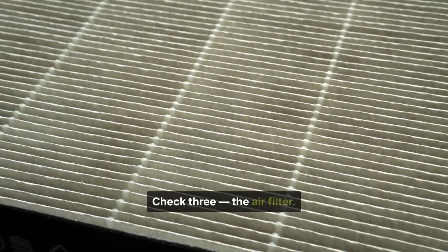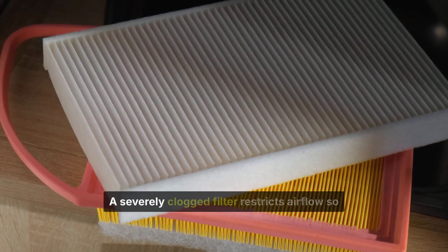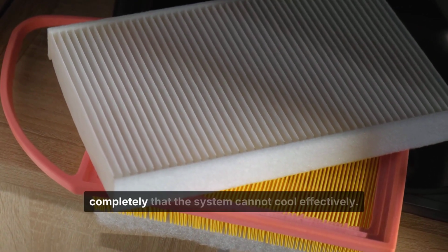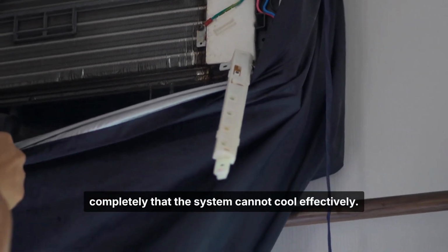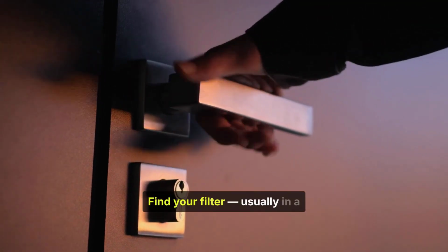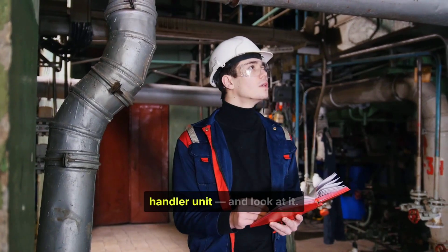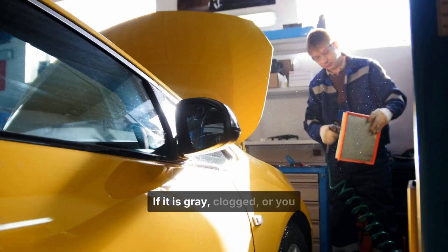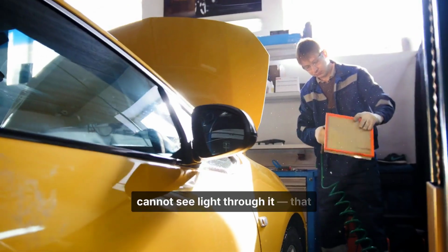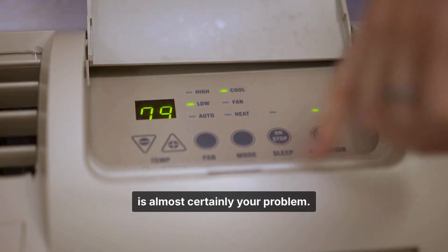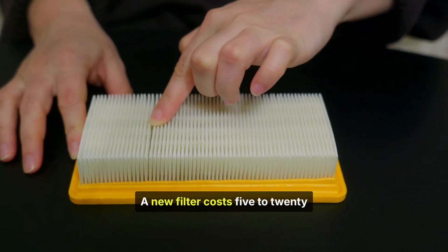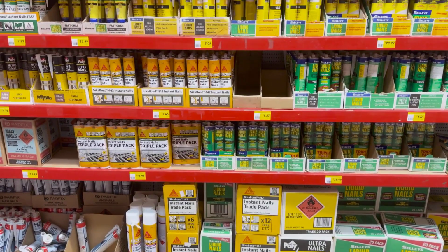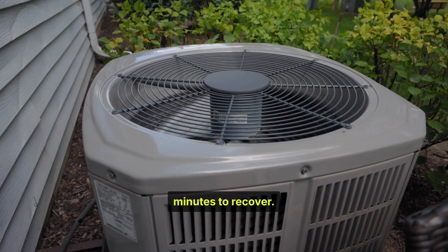Check 3. The air filter. A severely clogged filter restricts airflow so completely that the system cannot cool effectively. Find your filter, usually in a return air vent or in the air handler unit, and look at it. If it is gray, clogged, or you cannot see light through it, that is almost certainly your problem. A new filter costs $5 to $20 at any hardware store. Replace it and give the system 30 minutes to recover.